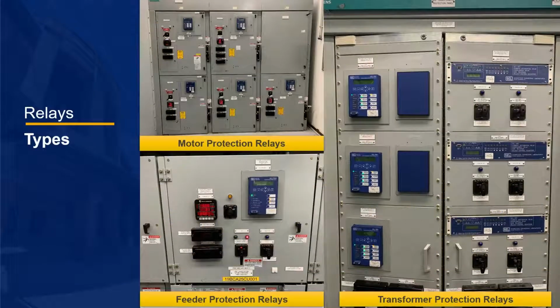In the next few slides, we want to go over some of the steps, inputs, considerations, and so on that went into the design aspects of the project and highlight some of the methodologies. For this project, we replaced 3 main types of relays: motor protection relays, feeder protection relays, and transformer protection relays. Each of the different relays provides different configurations, different forms of protection, and different software settings.